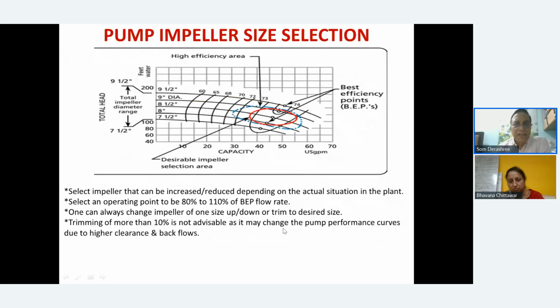So once you do the impeller size selection, select an impeller that can be increased or reduced depending on the actual situation in the plant. Select a pump operating point of 80 to 110% of BEP. So you see this 80 to 110 range is okay when you're selecting an application, because there will not be much of a difference, since this curve goes like this. Any point from here to here is all 74. From here to here, it's all 73. So not much change will happen. So you choose the point which is within 80 to 110 percent.